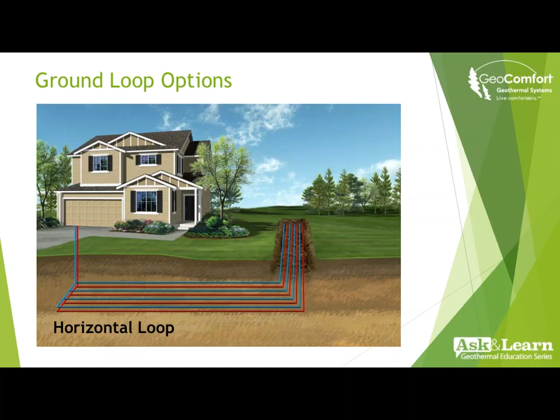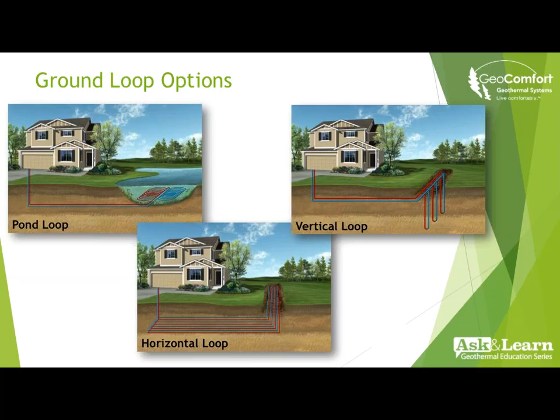When you go to vertical loops, those can be put into a real tight configuration, like in row homes in the area where I live - we can put these right down the driveway. Typically a 10 by 10 area will handle most homes in the 1600 to 1800 square foot range. You don't need hardly any space for vertical loops; they can punch holes in anywhere. The pipe is a polyethylene heat fusion pipe, so we don't have to worry about leaks or defects - it's got a 50-year pipe manufacturer's warranty. So when it's in, it's done.